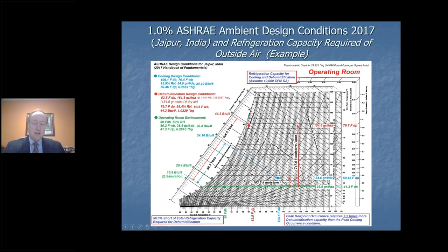To go from the peak dry bulb day, you would see that I would need to remove moisture, but only 103.5 pounds of moisture per hour. So that's a huge difference. Look at the amount of moisture removal. So if I had only designed what I would call the air conditioning system for that peak dry bulb day, I cannot dehumidify that much air. And then we wonder why we have moisture in our buildings.